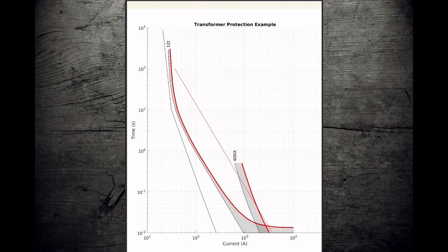And what this does is it gives you this sweep where it's the expulsion fuse that acts to interrupt, and then you get to here, and then the current limiting fuse acts to interrupt. And what that does in practice is it cuts this tail off the end, giving us a perfect protection of this transformer all the way along, with the possible exception of this very tip here on the 15K, which we already discussed.